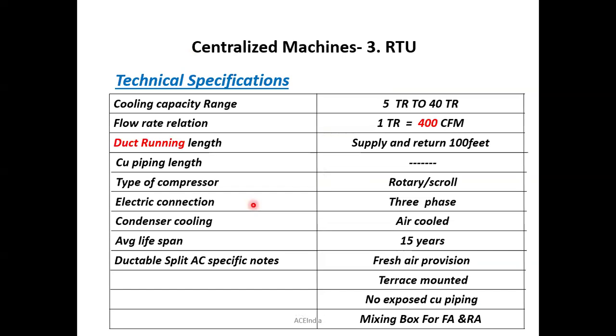Here, the cooling capacity ranges from 5 ton to 40 ton. Now, in the flow rate relation, again, 1 ton equals 400 CFM, and the duct running length is around 100 feet, both for supply and return. So that means you can simply connect the supply duct and return duct in an adjacent manner, and you can take out both ducts to that respective RTU itself.